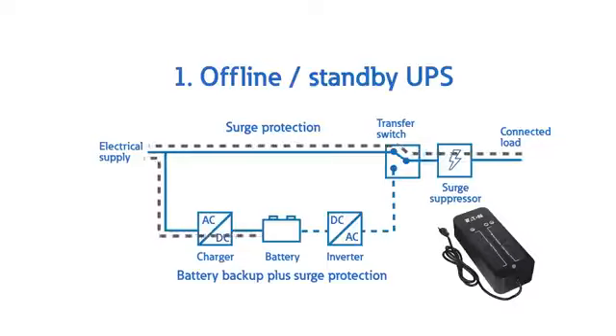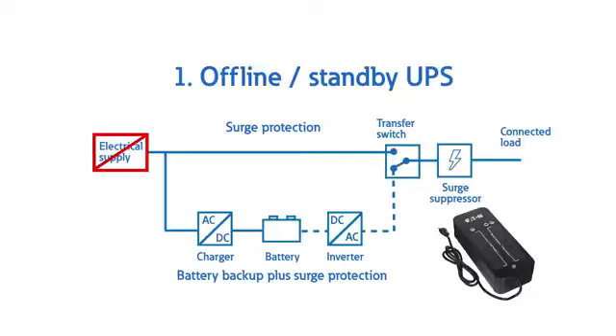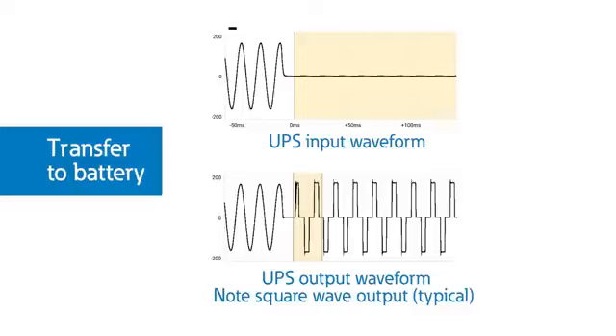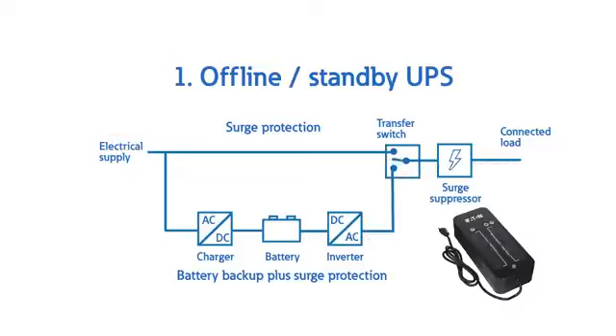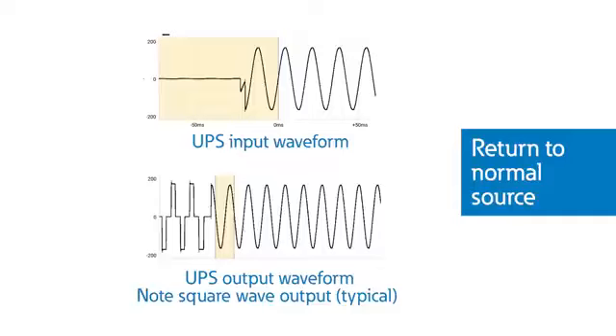First is the offline or standby UPS. This is a very basic battery backup system that waits for something bad to happen, and then once it senses a sag, swell, or full interruption that exceeds a predefined limit, it turns off the utility power connection and switches the load over to an inverter fed by a battery. The inverter converts DC power of the battery to AC to feed your loads. Once power is restored to an acceptable level for an acceptable period of time, the battery connection is turned off and the utility connection is turned back on. All of this switching is done with electronic switches that operate very quickly before the loads can drop out.